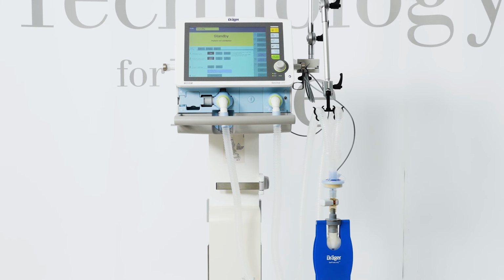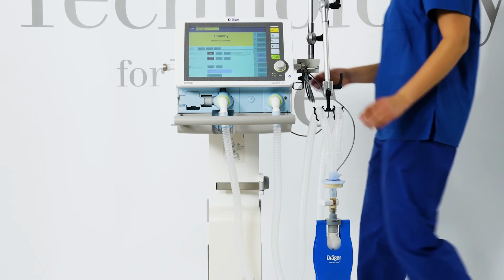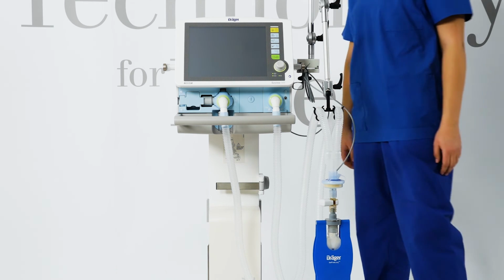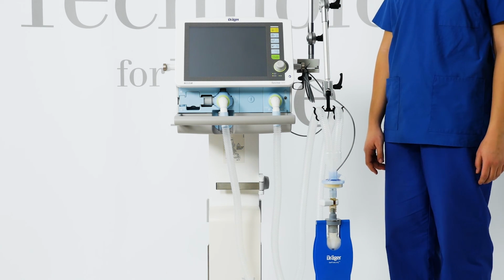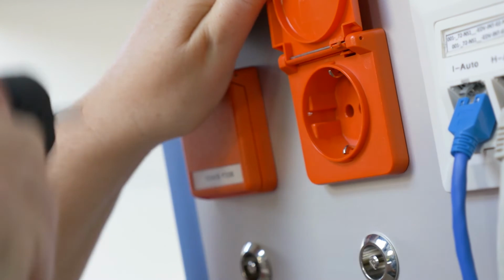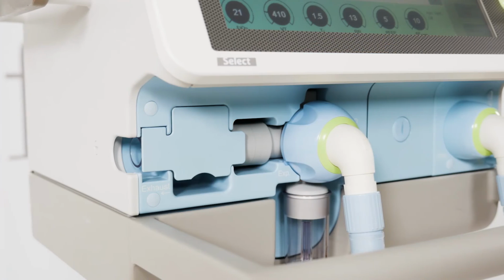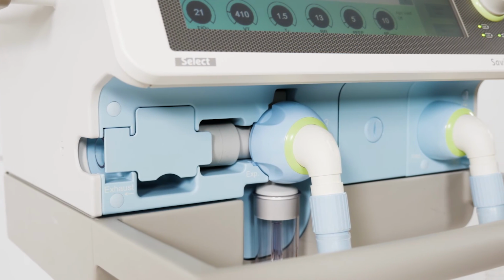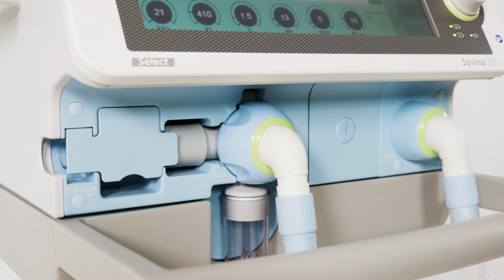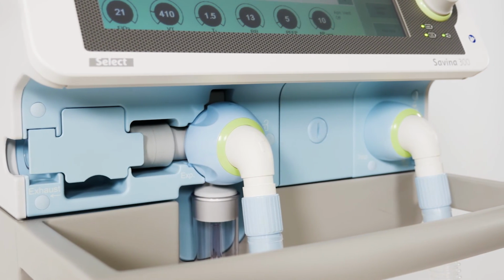This chapter describes how to disconnect the ventilation accessories, dismantle them for reprocessing, and which reprocessing methods can be used. Before you disconnect and dismantle the ventilation accessories, switch off the device and breathing gas humidifier and remove their power plugs. Drain the water traps and breathing hoses and, if present, the water container of the breathing gas humidifier.